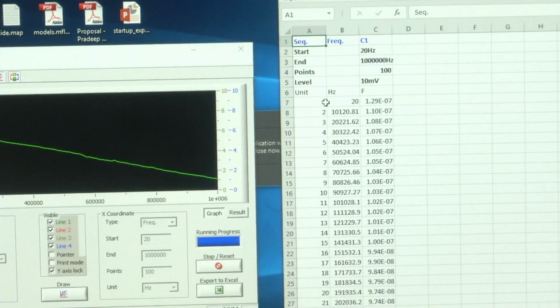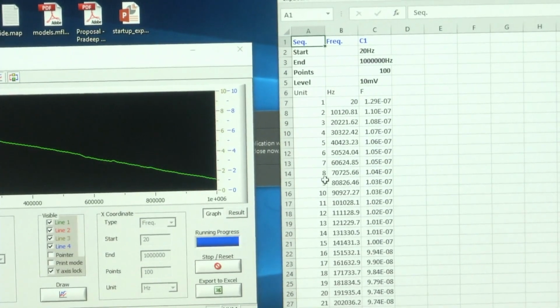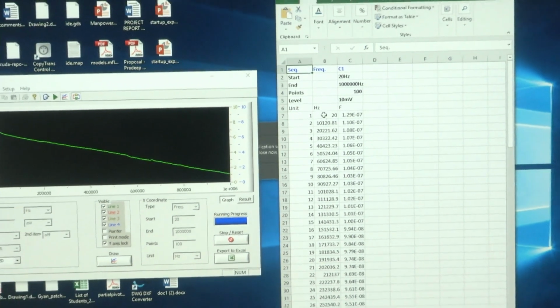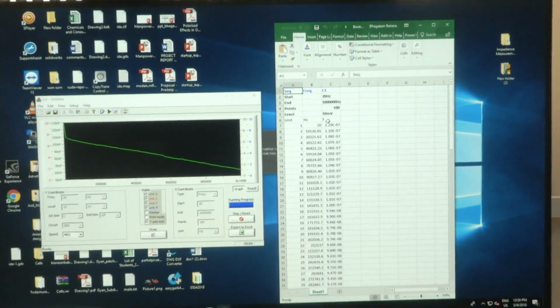See, this is the serial number of the reading, the x axis, which is the frequency, and the capacitance that is measured in farads. Let us see, 100 data points should have been taken. If you check it, you will see that there are 100 data points, and till around its operating condition it is staying within the 0.1 microfarad range. So, this is around 0.09 microfarad at a frequency of 363 kilohertz. So, this is how we can have a sweep.